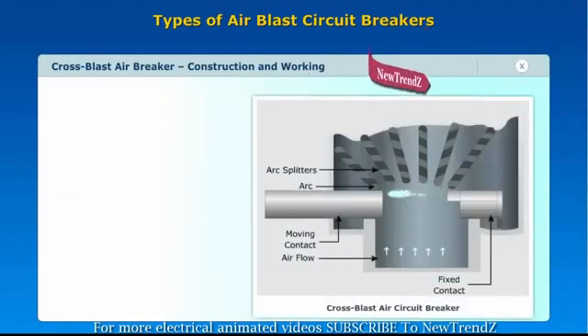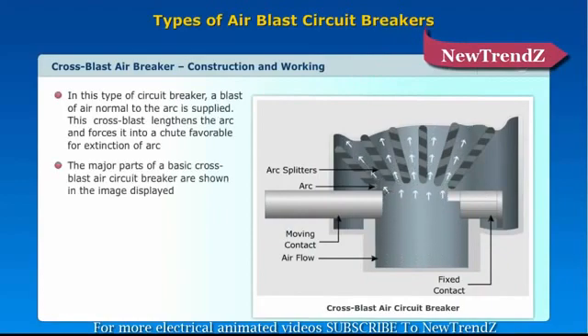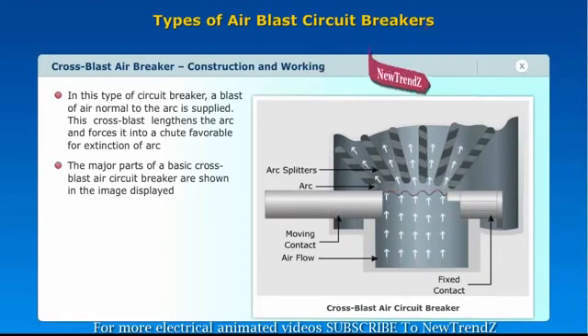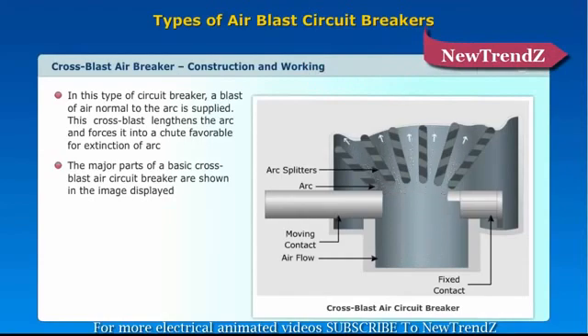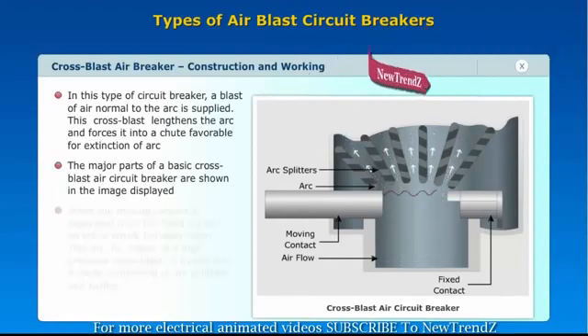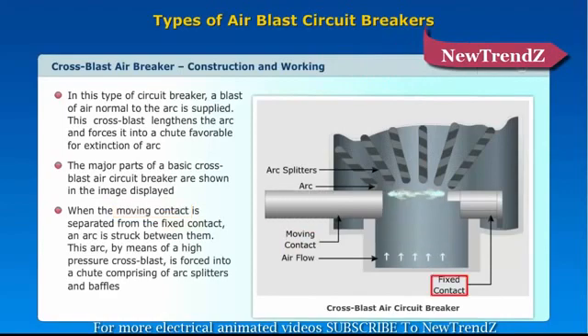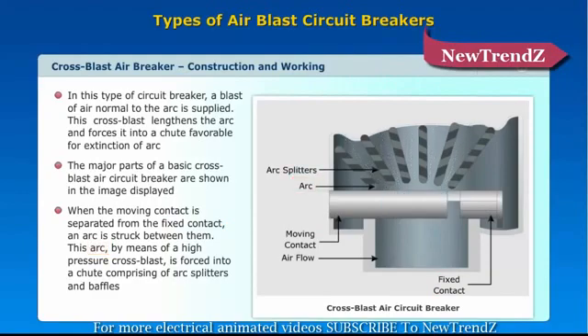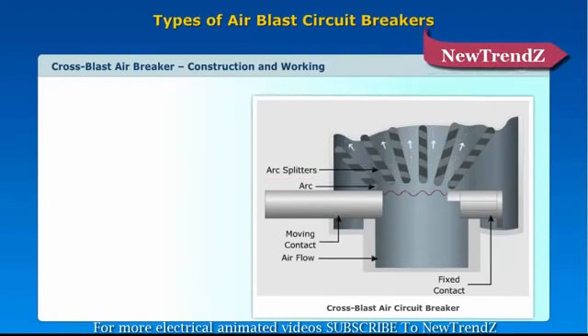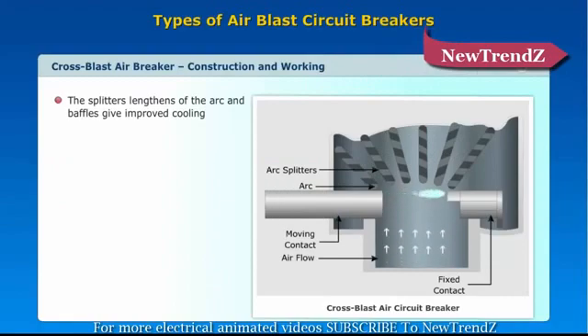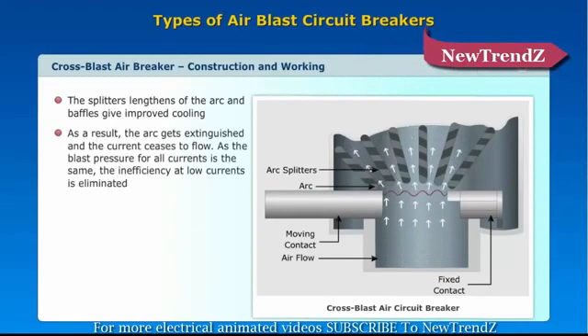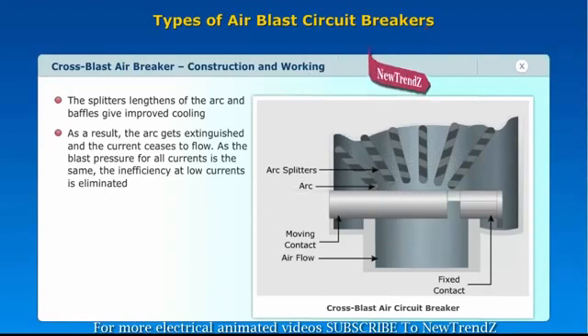Cross blast air breaker construction and working. In this type of circuit breaker, a blast of air normal to the arc is supplied. This cross blast lengthens the arc and forces it into a chute favorable for extinction of the arc. The major parts of a basic cross blast air circuit breaker are shown in the image. When the moving contact is separated from the fixed contact, an arc is struck between them. This arc, by means of a high pressure cross blast, is forced into a chute comprising arc splitters and baffles. The splitters lengthen the arc and baffles give improved cooling.